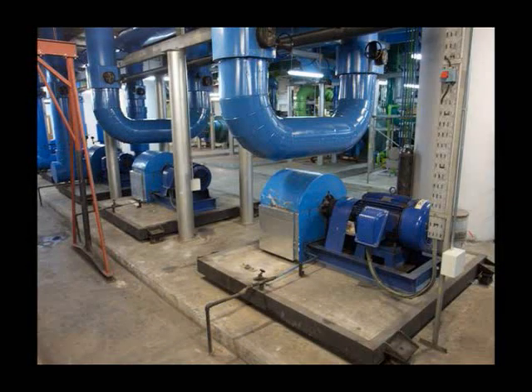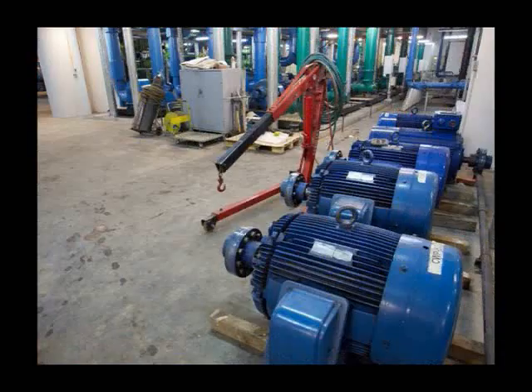I mentioned before, my mission in life is to get rid of control valves and primary-secondary pumping. So we are down to primary pumping. So we do a bypass. This is a quick way. So there are a lot of pumps here for sale in case anybody needs pumps, you know. And this motor, I'm told, was new. They just bought it because the old one burned out, 20,000 Singapore dollars. Then we came in and took it out. These are 175 horse and we put in 40 horse.